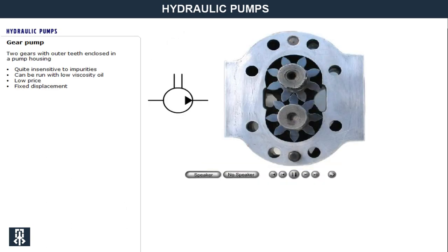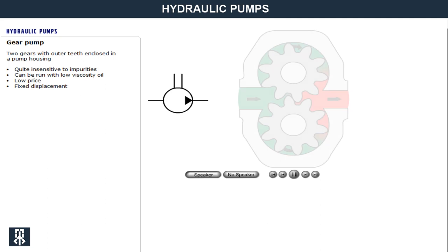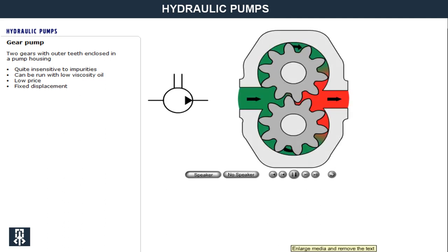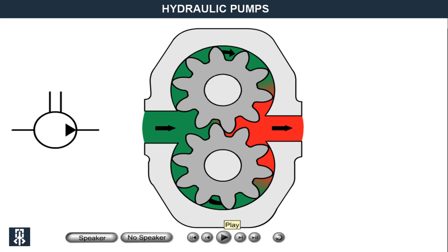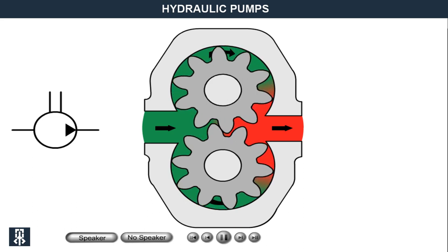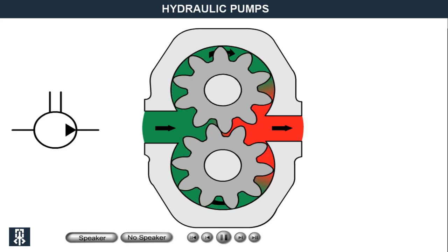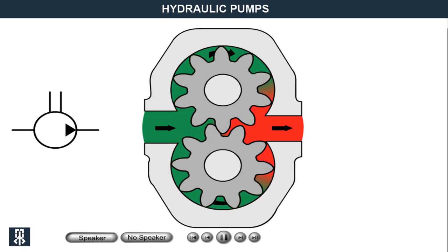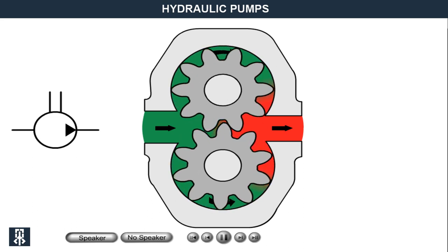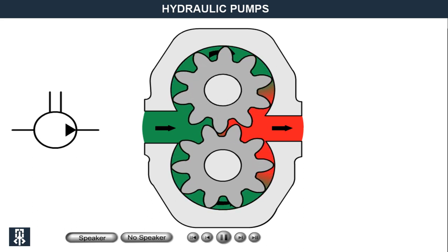Gear pump. A common type of pump with fixed displacement in a hydraulic system is the gear pump, with two gears with outer teeth enclosed in a pump housing. The oil moves in teeth spaces along the housing's inside from inlet to outlet. Depending on the pump's design, it gives a pulsating flow.